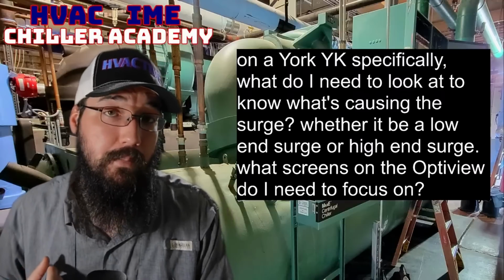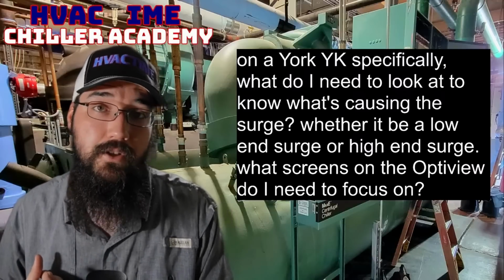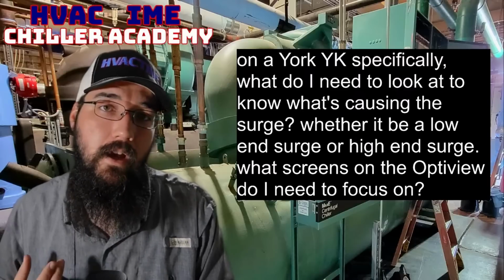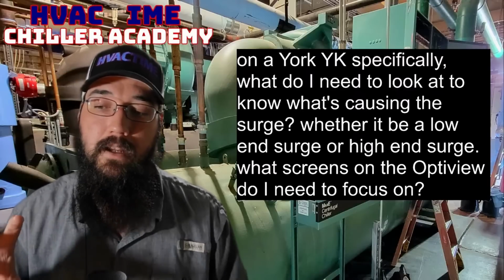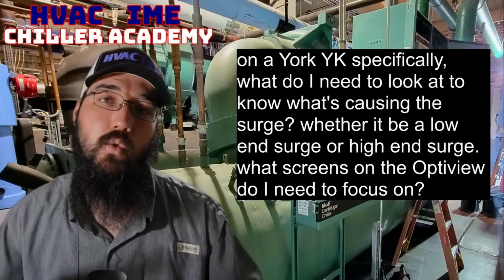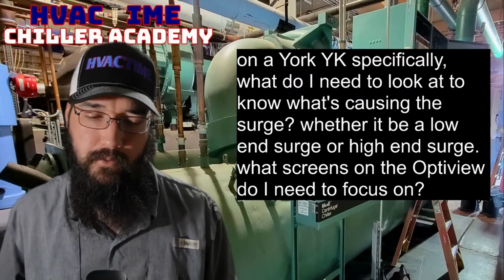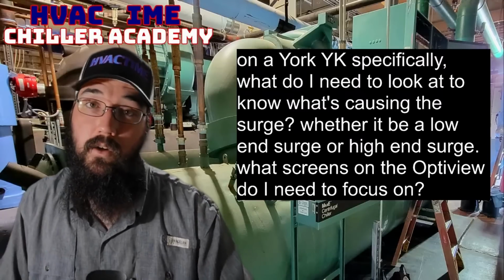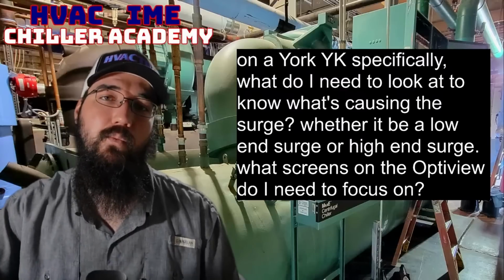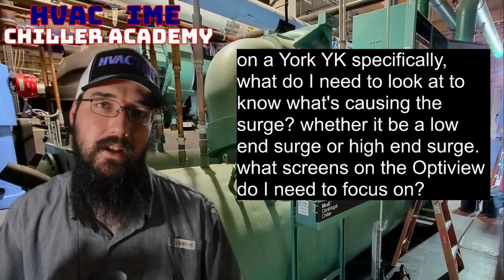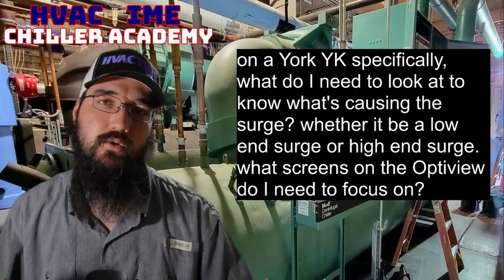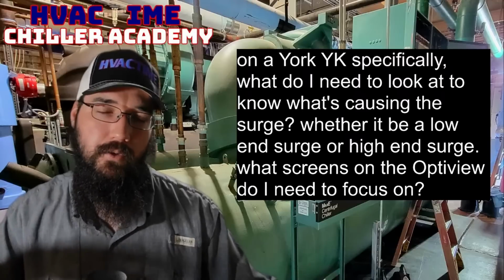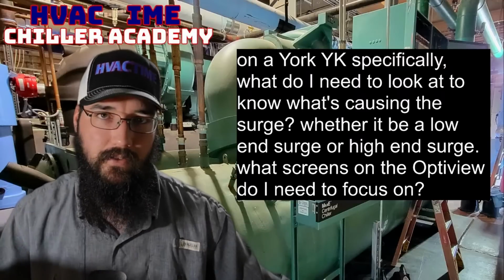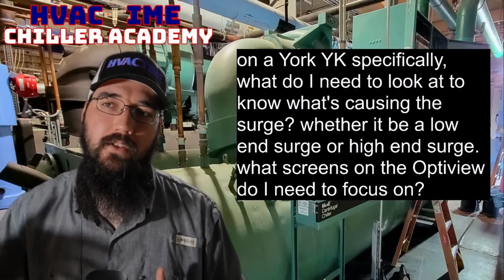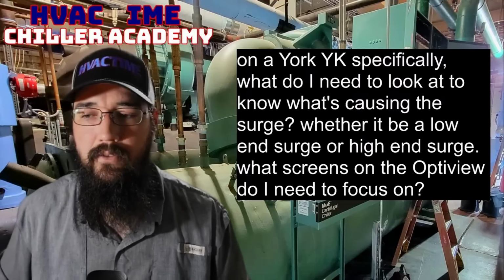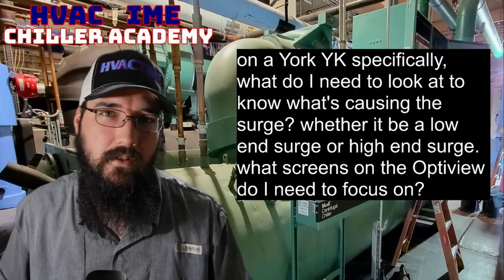You could have an issue at the impeller, especially if you've had a major surging, you could have had some touchdowns that could tear up some of the impeller. By touchdown, I mean the impeller actually making contact with the interior walls of the compressor. So that's going to shave off some of your aluminum. If the impeller starts to get damaged, it will struggle to maintain lift, even though the conditions should be right. You've got proper GPM, you've got a stable load condition, refrigerant's in the right condition, all of that set. Then you have to start asking, okay, what internal compressor issues do we have? That's the next phase of that troubleshoot.